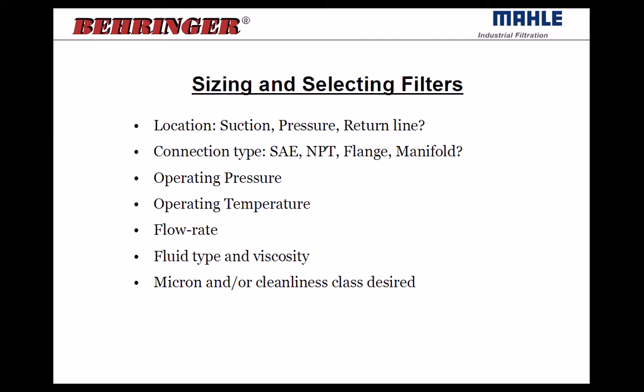And to properly size, we need at minimum the operating pressure, the operating temperature, the flow rate, fluid type and viscosity, and the micron or the cleanliness class desired. Those are the minimum things that we'll need in order to properly size the filter.